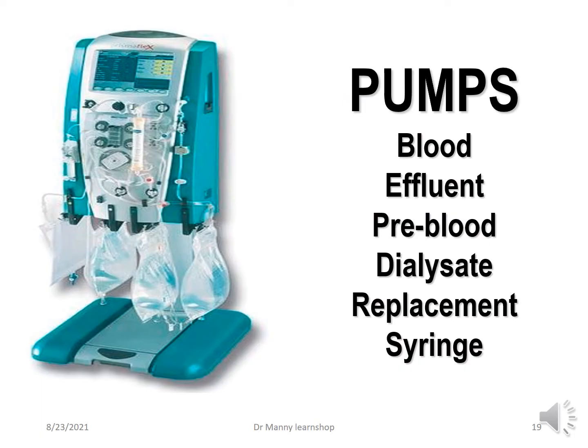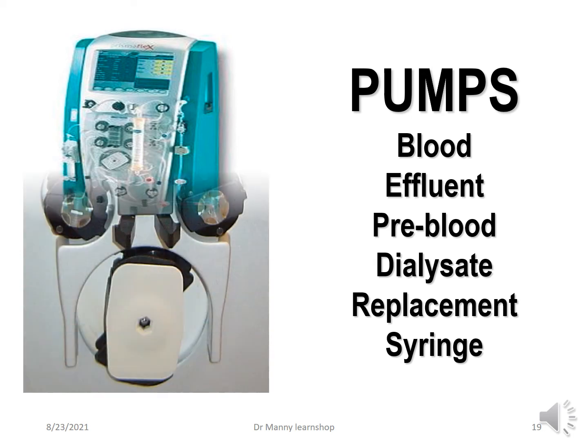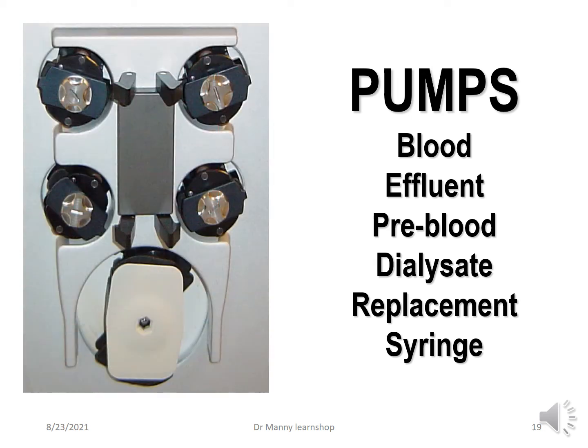Then you've got the pumps, and you've essentially got 6 pumps. You've got the blood pump, the effluent pump, the pre-blood pump, the dialysate pump, the replacement pump and the syringe pump. Now the blood pump moves the blood. The effluent pump pulls out fluid and puts the fluid into the effluent bag. The pre-blood pump puts in replacement solution or substitute solution before it goes into the blood, diluting the blood. You can have dialysate solution and replacement solution and a syringe driver as well. The syringe driver would be for heparin.